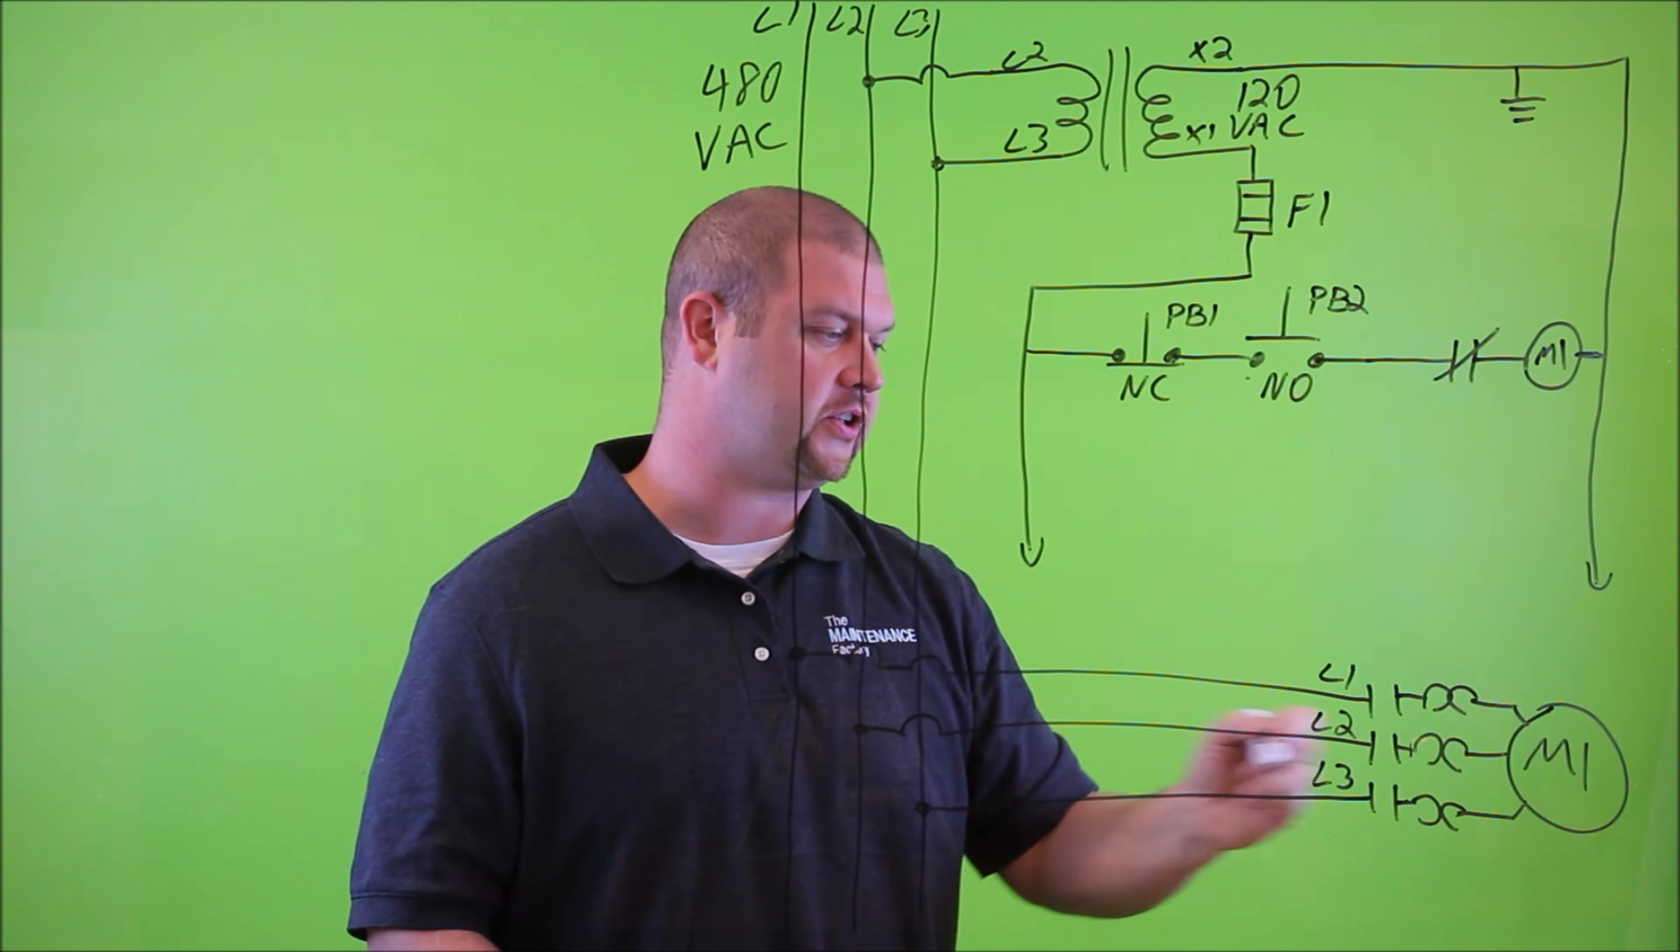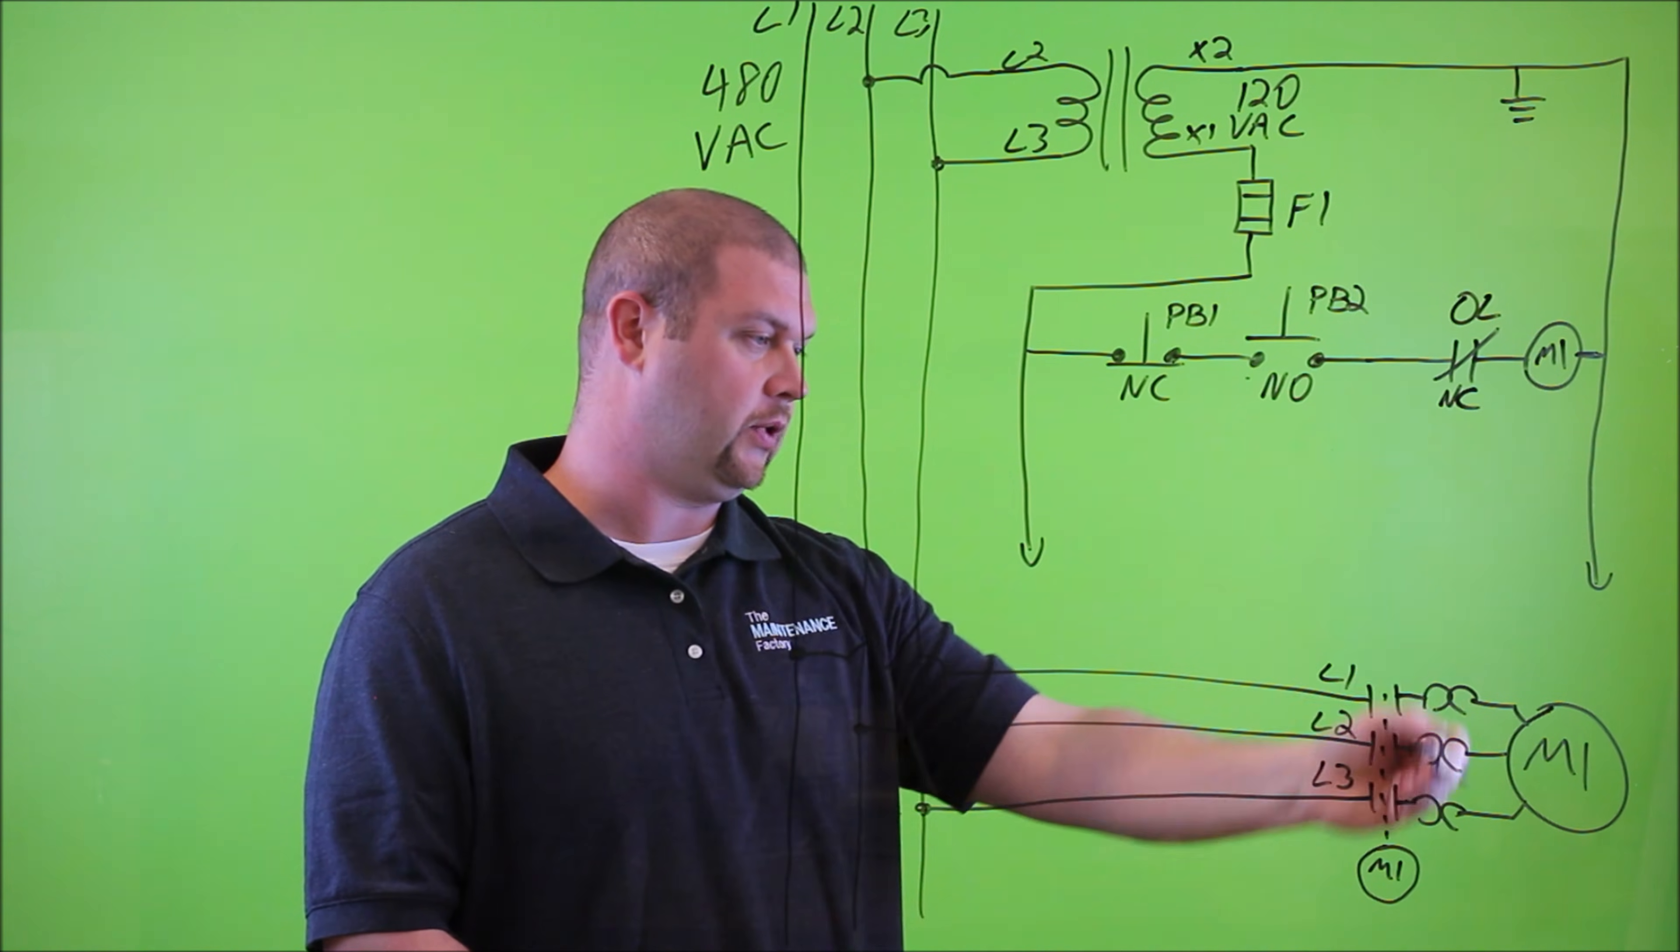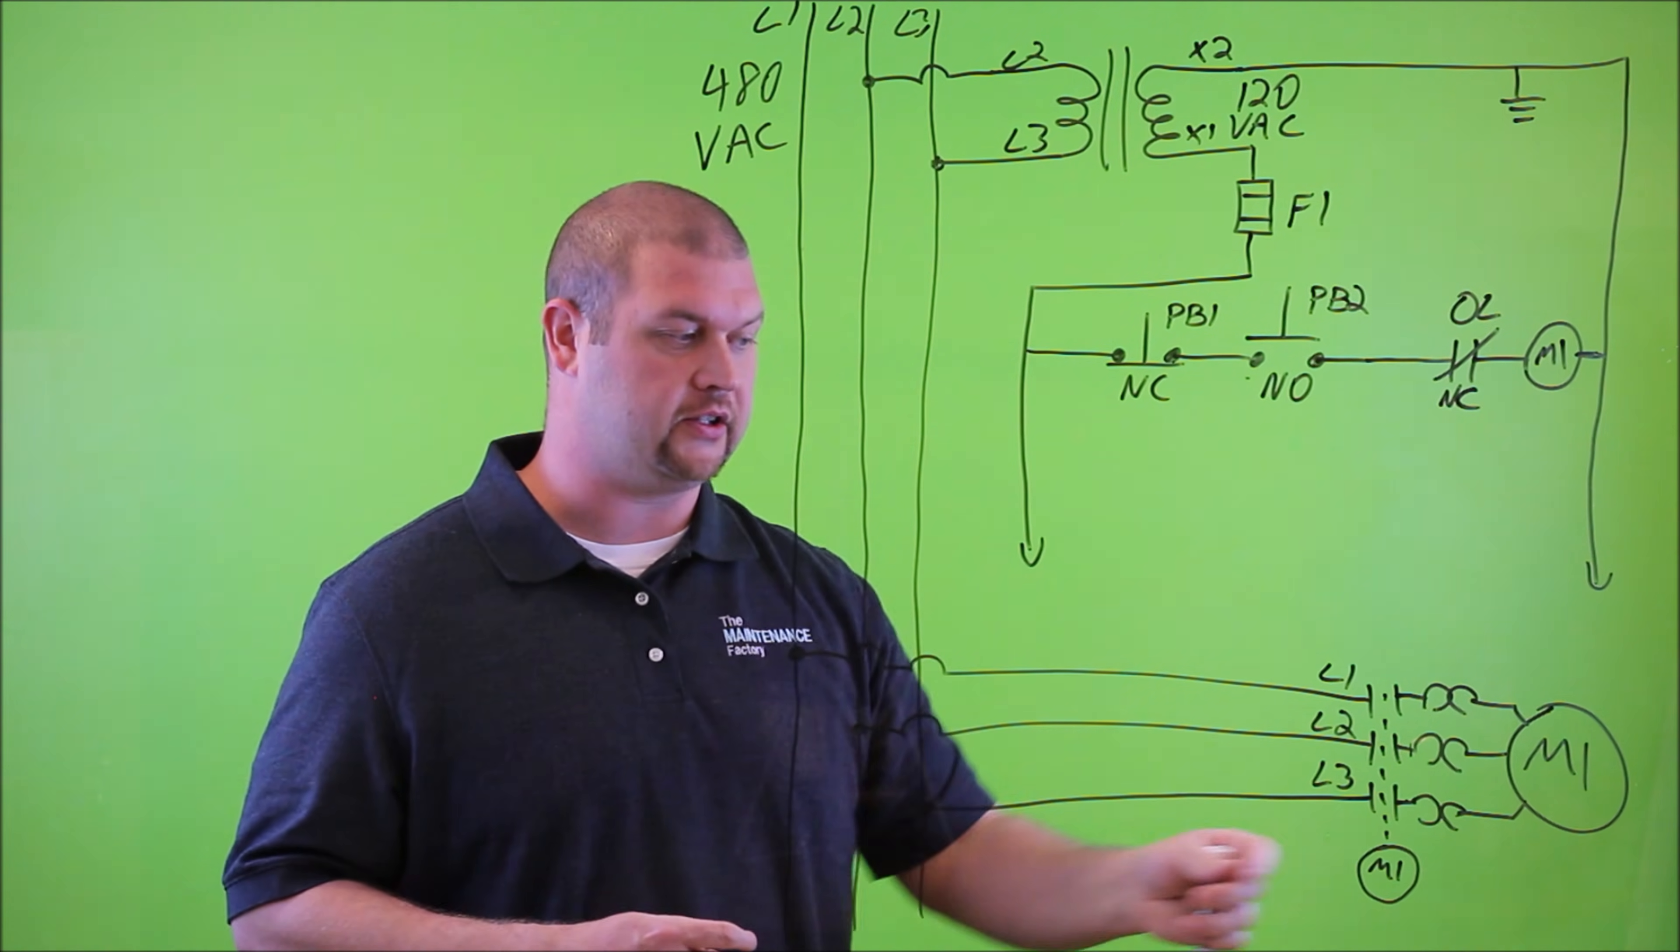Now, up here we have our control power transformer, which is connected to L2 and L3. It's taking 480 volts AC, and it is stepping it down to 120 volts AC, and then that 120 volts AC is what we're going to use to control the state or the condition of this contactor. Now, we have the coil that's going to control this contactor, and there's some physical connection between this coil and these three contact points here. And then we have the normally closed button. And it's related to this overload portion right here. And then we have our stop button, which is normally closed, and it's labeled as PB1. And then we have a start button that is normally open, and it's labeled PB2.